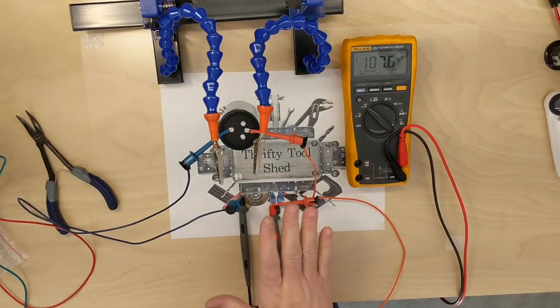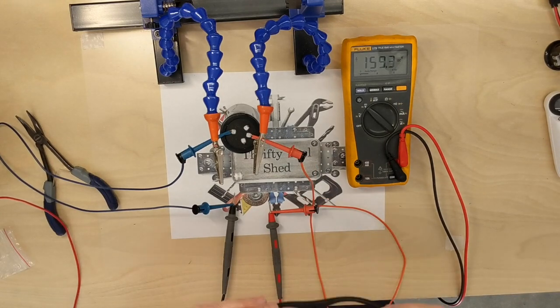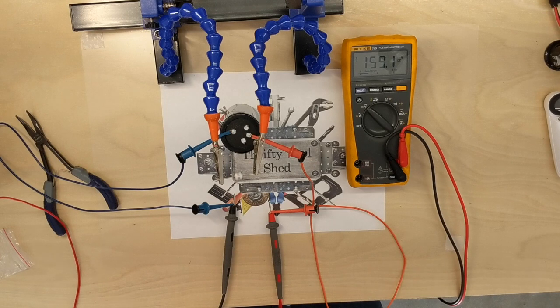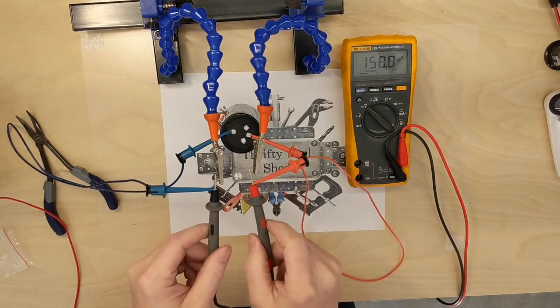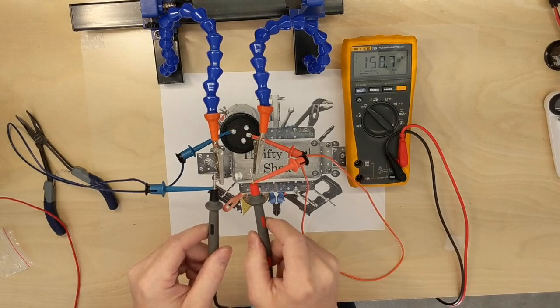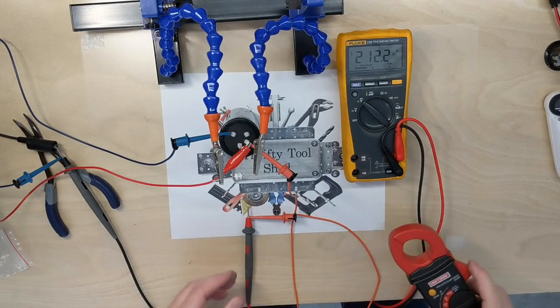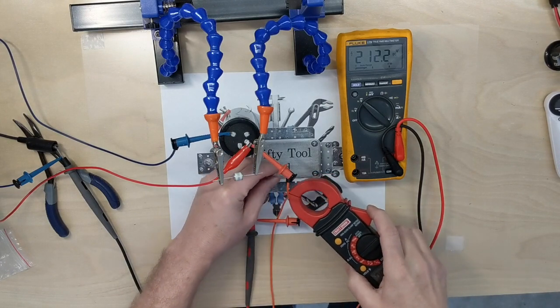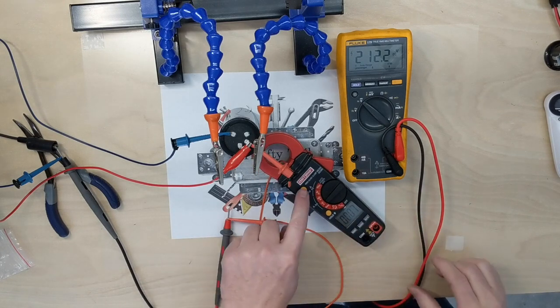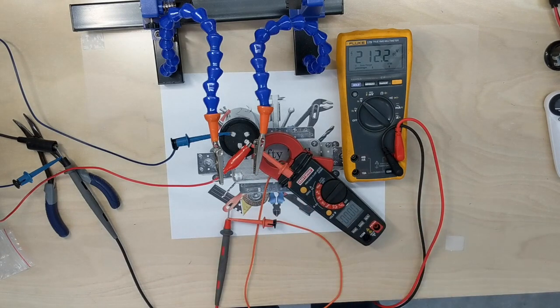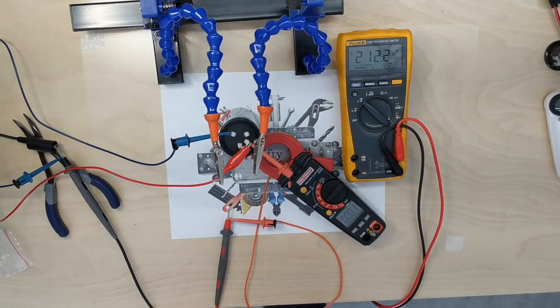Now at 160 volts, I'm gonna make sure I have my safety glasses on. 160 volts, we still shouldn't see any drop across it, any current. It's still not enough to ignite the gas. Now I'm going to bring in an actual amp clamp, so we can actually see at 212 volts if we get any current at all.